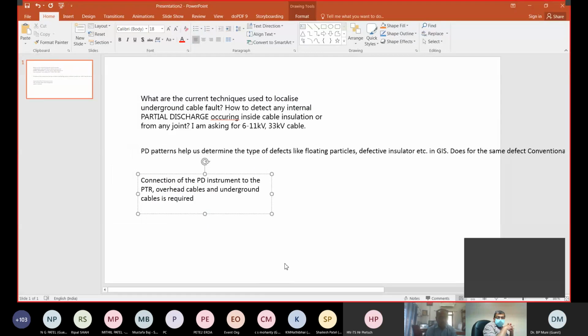It's very important because in some cases the test frequency is different for the instrument transformers and for the cable, and also the amplitudes. I know it definitely for a cable and a GIS, and also for the instrument transformers in the GIS, that you have to be very careful to apply higher voltage levels. And if the instrument transformer is connected to the GIS and operating, normally you have to go to higher frequencies, normally more than 100 Hertz, or you have to disconnect the instrument transformers. So I don't know about air insulated instrument transformers. You have to look at the technical description of this instrument transformer, whether it's allowed to test with the same voltage as the GIS and with the same frequency. You have to look at the spec.